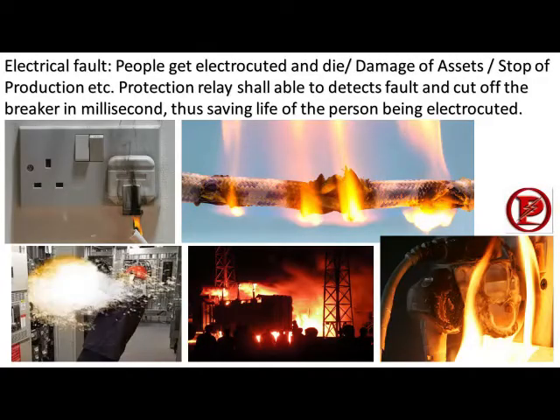When an electrical fault occurs, people can get electrocuted and die, because the return current flows through their body, stopping their heart. Therefore, the protection relay must be able to detect the fault and cut off the current flow by opening the switch in milliseconds.